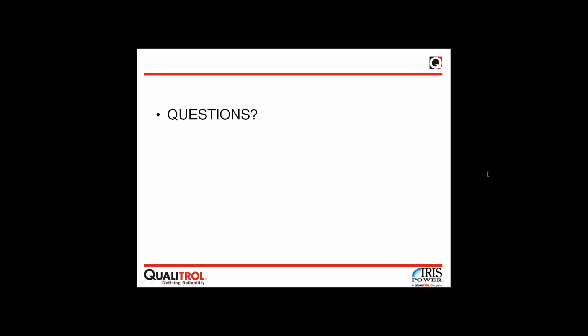We have a question that came in. It says, do we need one GARD per generator, or can GARD monitor more than one generator? Depends on the technology. If it is flux only, we can dedicate one instrument to up to four machines. However, that is a single technology approach. If you want to combine technologies within one monitoring instrument, which is a GARD, in that case you do need one GARD per rotating machine because of the layout of the internal boards.